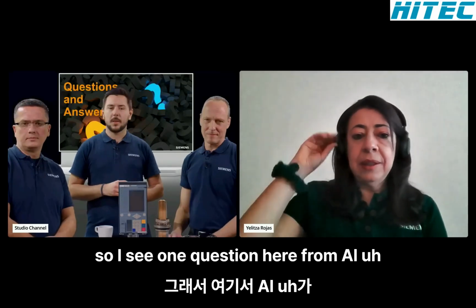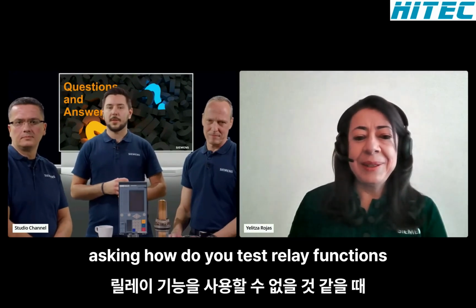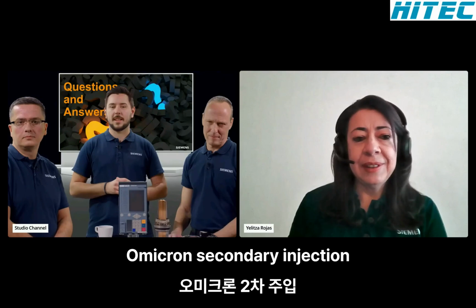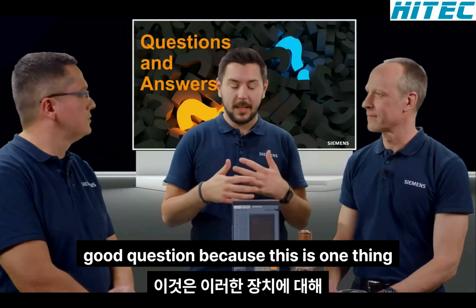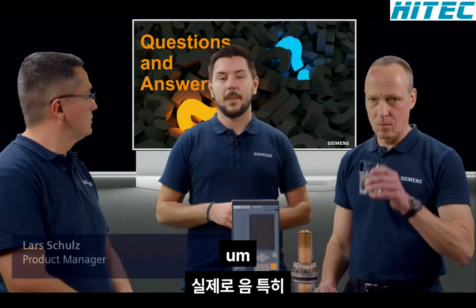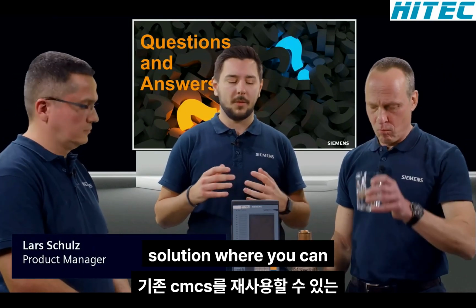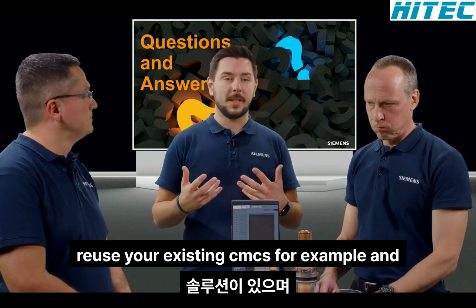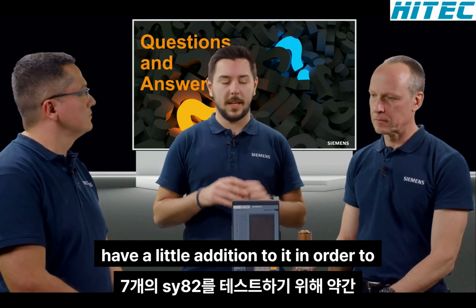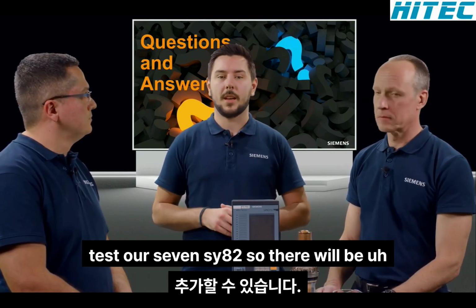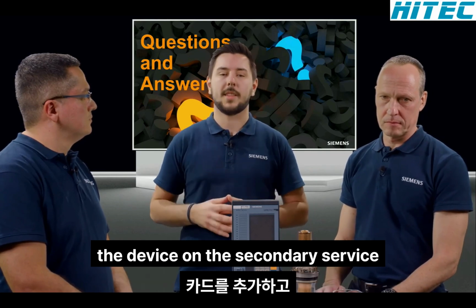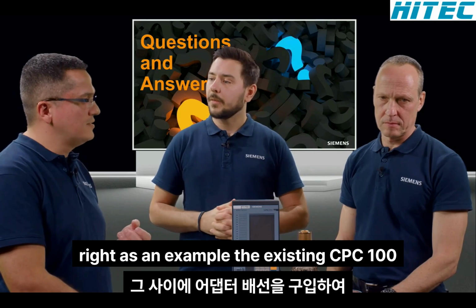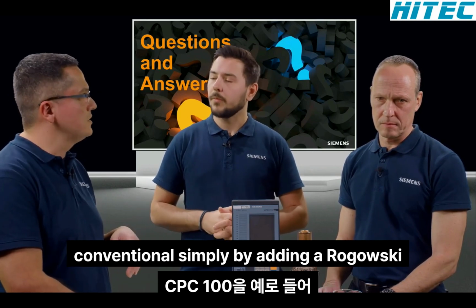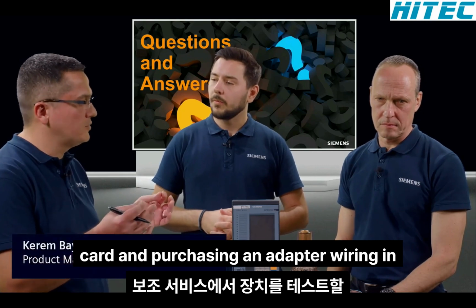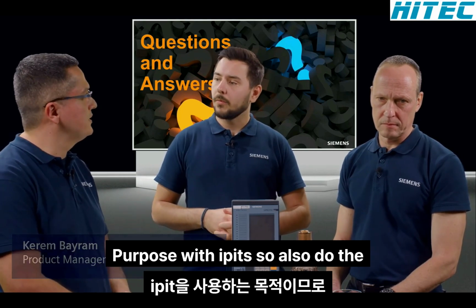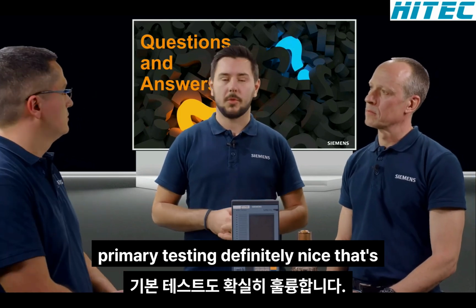I see one question here asking, how do you test relay functions when it seems like you cannot use Omicron secondary injection? Good question, because this is one thing that would mainly change for those devices. But actually, especially from Omicron, there is a solution where you can reuse your existing CMCs, for example, and add a little addition to it in order to test our 7SY82. So there will be options available for you to also test the device on the secondary side. That's right. As an example, the existing CPC100 from Omicron, which we use for conventional, can be used for the same purpose with LPITs simply by adding a Rogowski card and purchasing an adapter wiring in between. So also do the primary testing. Definitely. Nice. That's cool.